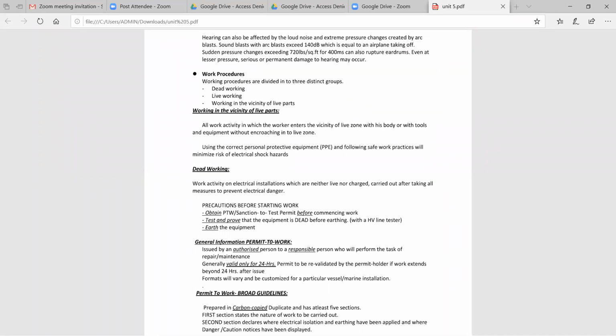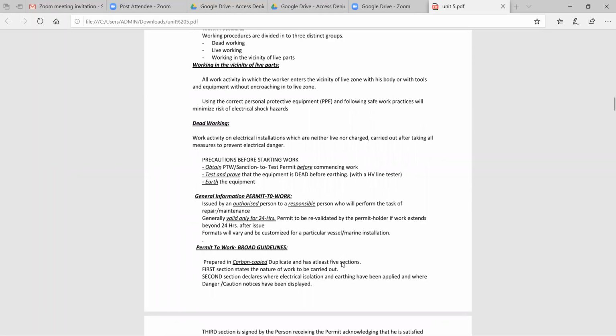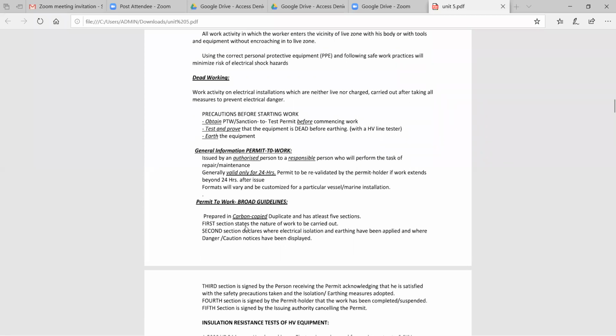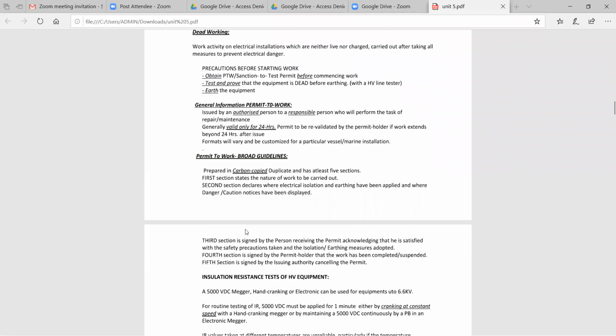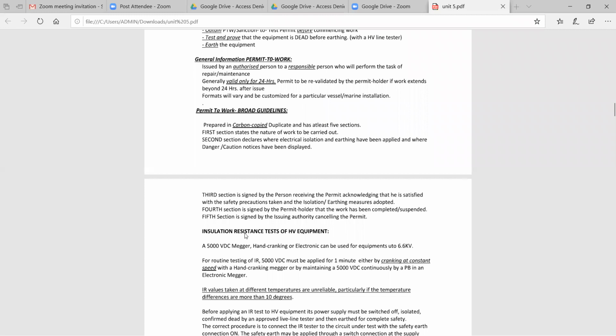So for dead working, general information on the permit: it is valid for only 24 hours. And then the permit to work broad guidelines, which has a carbon-copied duplicate of at least 5 sections. The first section says the nature of work. The second section is for your declaration. The third is for the danger section, as well as the signed person receiving the permit. The fourth section is for the permit holder, and the work has to be completed. The fifth section is signed by the issuing authority for cancelling the permit. So this concept is to be considered for the work permit.